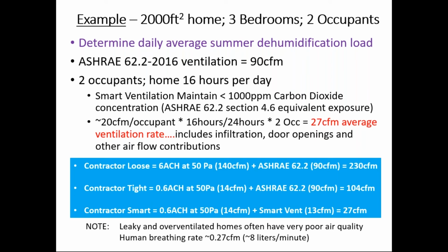Contractor Tight, who has looked at how to build a quality home that's very well sealed, has 0.6 ACH, which results in 14 CFM rather than 140, but still 90 CFM for a total of 104 CFM of infiltration and ventilation air.